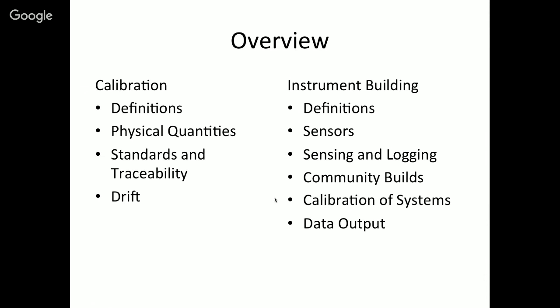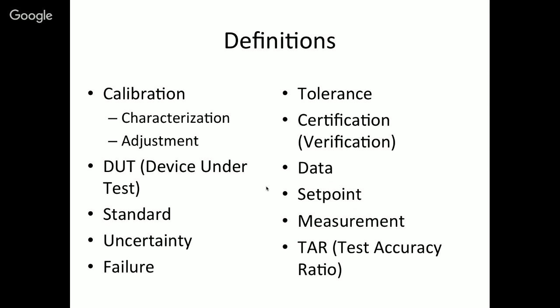All right, so moving right along. Calibration. Here we get into the definitions. Everybody seems to think that calibration is something that's just done, or sometimes it has the appearance of somebody waving a magic wand and saying, boom, you're calibrated. I'm here to tell you that calibration involves a two-step process that's repeated over and over and over again. You can only trust the calibration of a device for so long. And the calibration itself is broken down into two parts. Characterization, where you see how something works, and then adjustment, where you modify it. But then you have to go back to characterize it again and make certain that it's actually working. And then you adjust it again if you need to, and then you characterize it again, and then you get the idea.